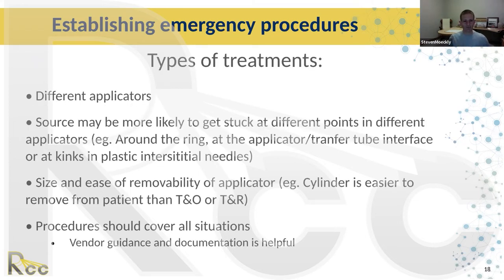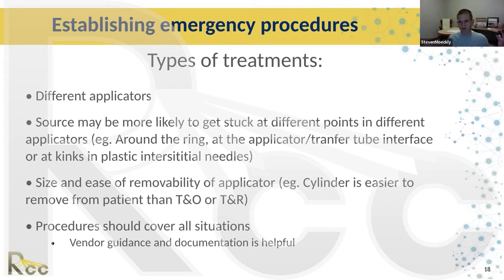Different applicators mean the source is more likely to get stuck at different points. The size and ease of removability is important, and the procedure should cover all situations. Vendor guidance and documentation is helpful. If you have limited communication with the vendor, utilize another physicist you know — that's important.